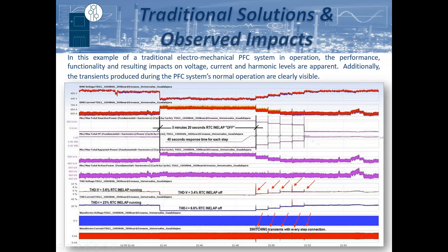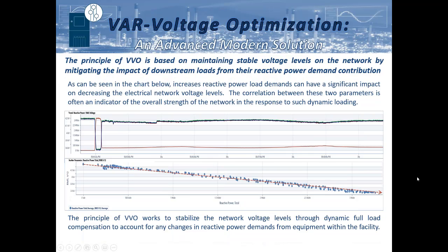Those transients are going in and breaking down the insulation on those capacitors, because when that contactor hits, all three phases are engaged at the same time and at a random state, right? So it's going to induce that transient. So it's not uncommon, walking through a facility, to see power factor correction systems that are just locked out and tagged out, or nobody knows if they're really working or not. And most of the time they're partial at best.